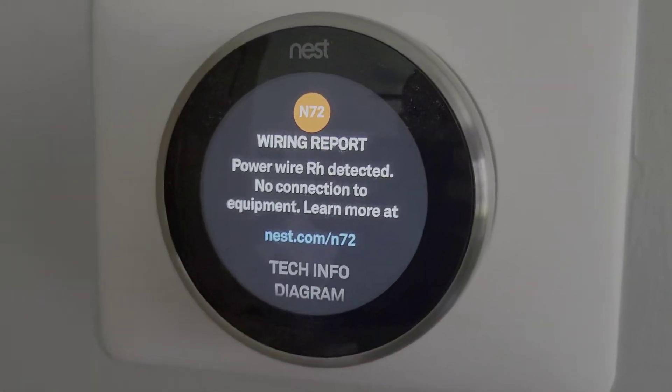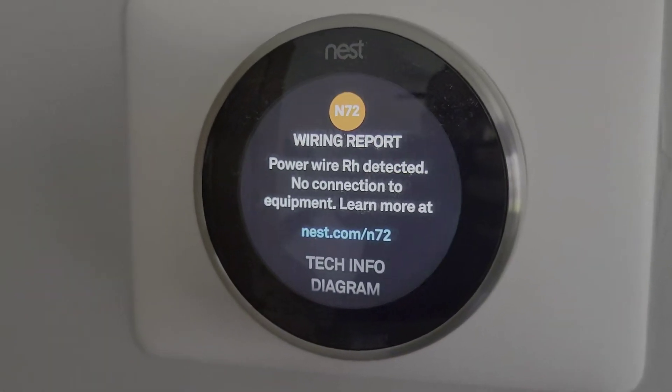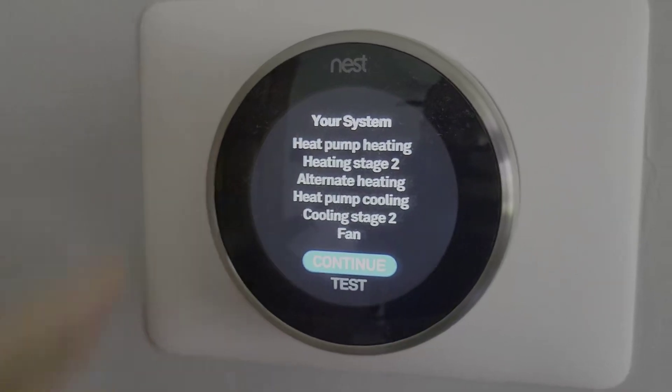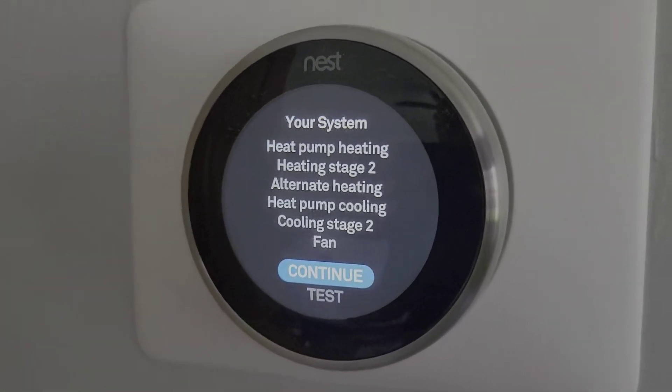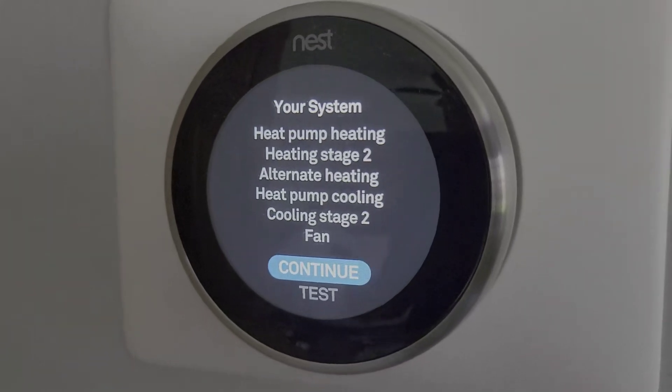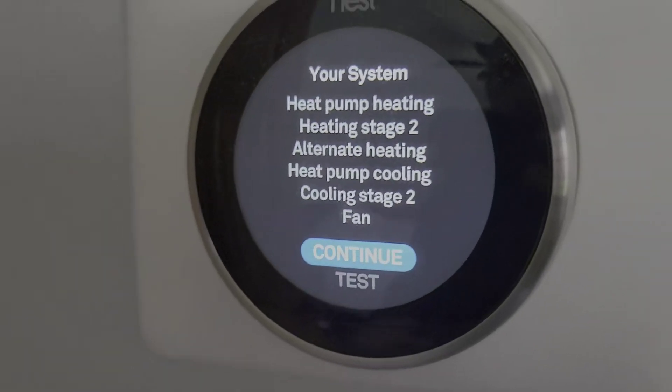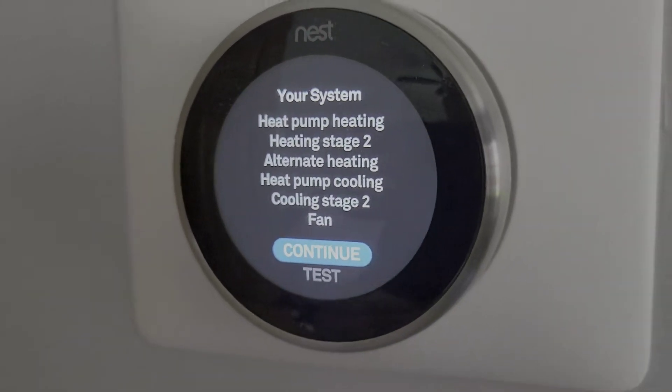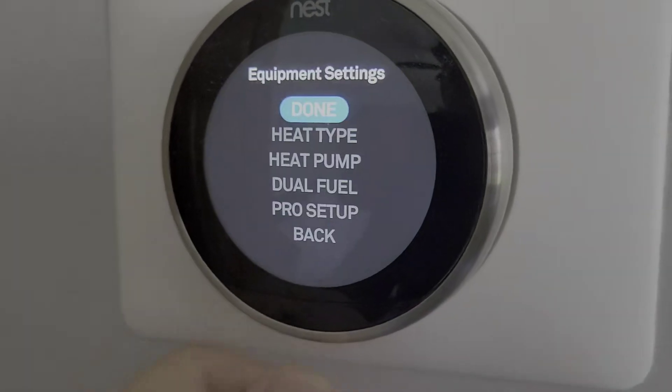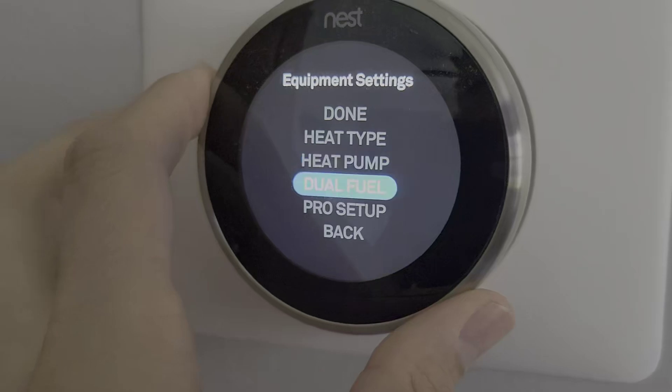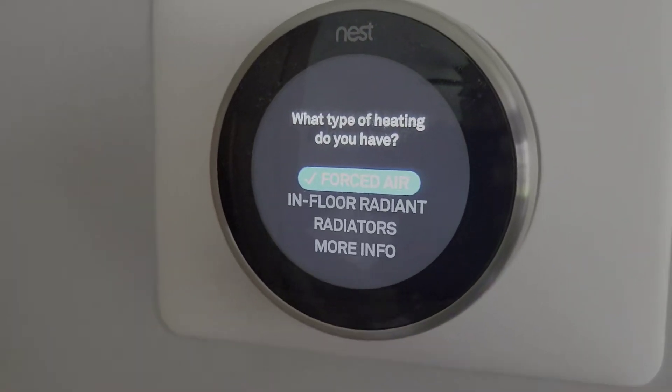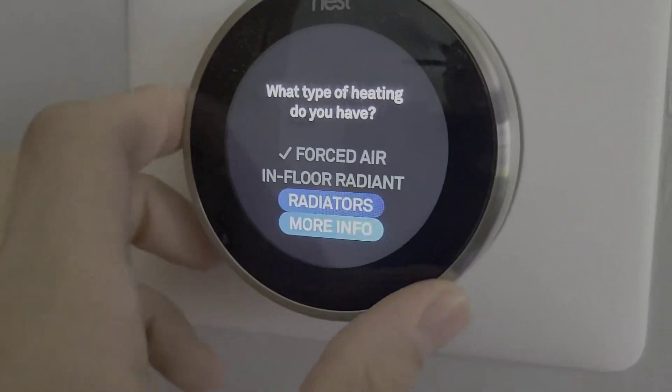Continue. It's going to tell you, hey, power wires detected, no connection to equipment. Again, not that important. All right, and it's showing you what all is available to you. So heat pump heating, heating stage two, an alternate heat, heat pump cooling, cooling stage two, and a fan. And you could test through the various things there. Probably one thing I want to show you that's important. Again, when you click on heat type, that's where it's going to let you say like, hey, forced air. One thing that's important is the heat pump setting.